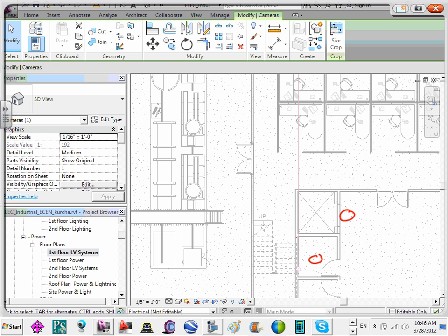You're also going to have 4 relay modules. The relay modules are your primary, secondary recall, your firefighter helmet, and your shunt trip. The shunt trip is going to turn off the electrical system in case there's water coming in there. You've got your primary recall. So if there's a fire here, the system knows that this smoke detector is sensing it. It's not going to open up the doors in this level, it's going to go to the alternate level, the secondary level, and open up there for egress.